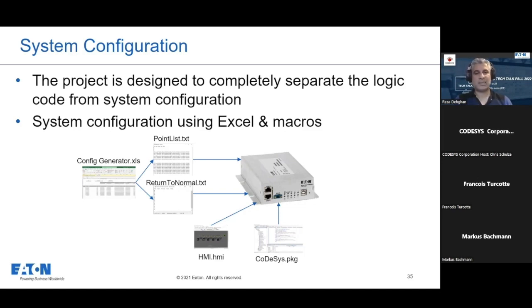So using that config generator, basically you just need to say, okay, I have 2 branches, and in each branch I have that many transformers, and then you just put the name of the points for status or for fault. And once everything is okay, when you hit execute on that macro, the macro also generates all the necessary automation functions, and it also creates the pointlist.txt and return to normal.txt. So it makes it more error resistant, and it speeds up the process of configuration.